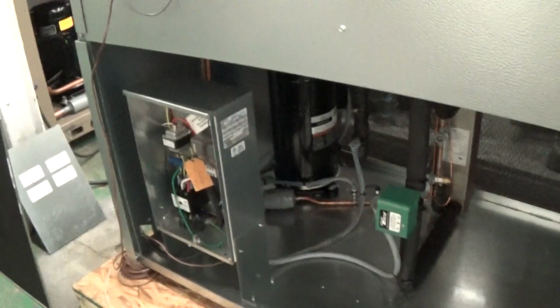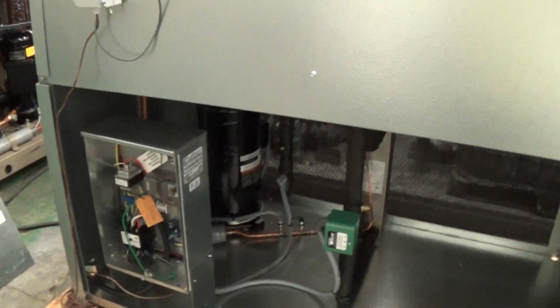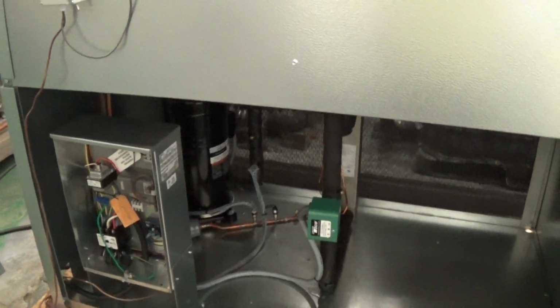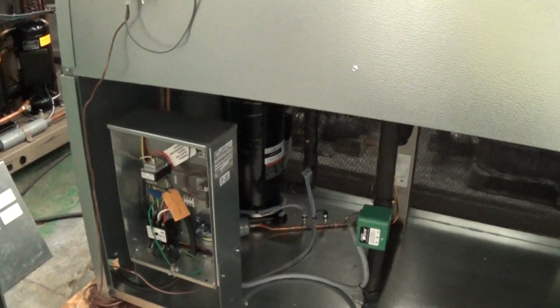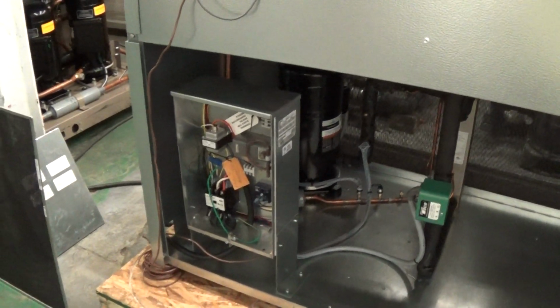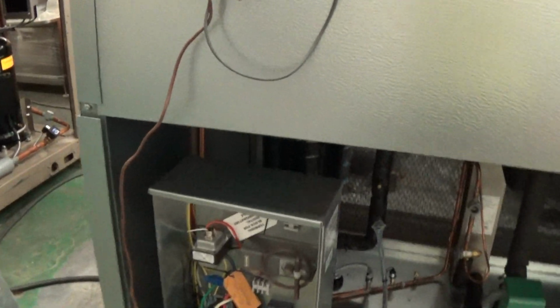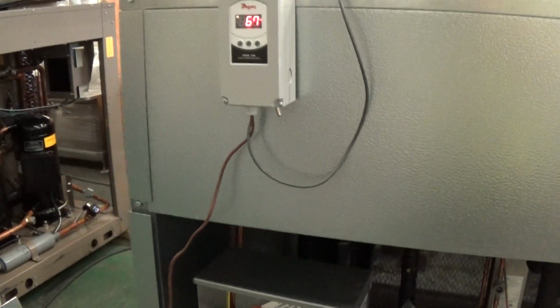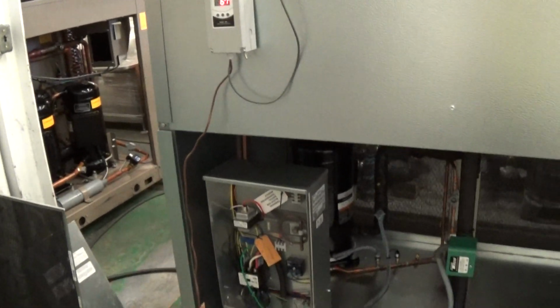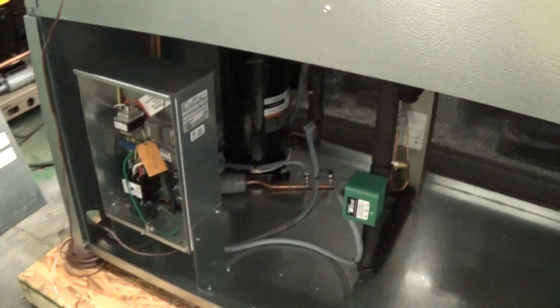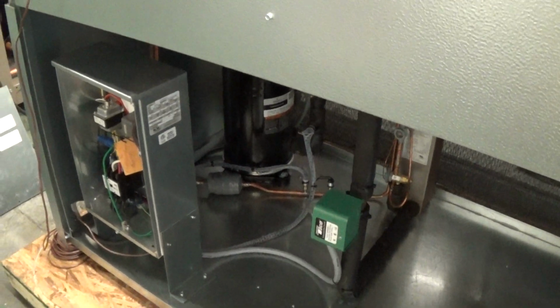So this chiller, if you're going to run it regularly but turn it off every now and then, you should leave the main incoming power on at all times. And you should turn the unit off just by the toggle switch that you see here. Because when you turn it off by the toggle switch, we still have live power going to the heater on the compressor, and that's important.